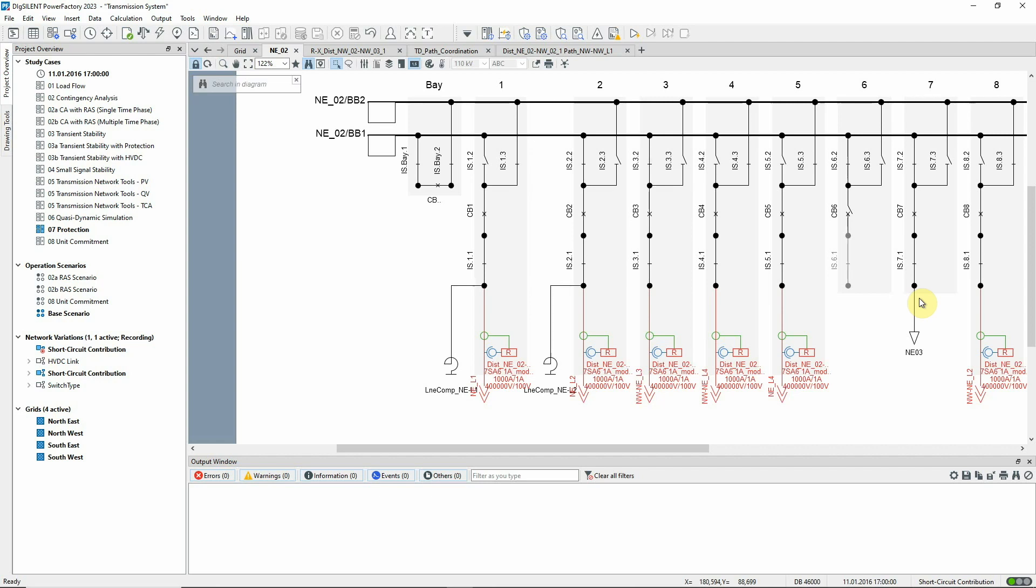The relays have already been configured. The zone reaches are calculated according to the cumulative method and the starting units are set to overcurrent apart from those in the north-west grid which only have impedance starting.